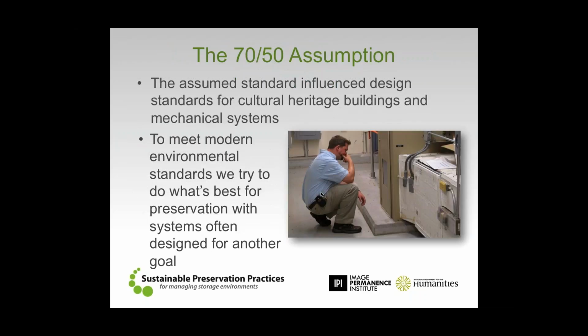As we started constructing more and more buildings and cultural institutions to these standards, we assumed that we wanted very tight control with not a lot of fluctuation in temperature and relative humidity. If we look back, say 20, 25 years ago, we assumed that the human comfort condition, 70 degrees, 50%, was best for what the collection needed. Then we found ourselves with a relatively new building that is only equipped or designed to achieve this very limited type of operation. You find out that you're limited in terms of dehumidification to roughly 70 degrees and 50% RH, or a 50-degree dew point, and that by and large the system is operated constantly, trying to achieve these very tight conditions and very tight standards.